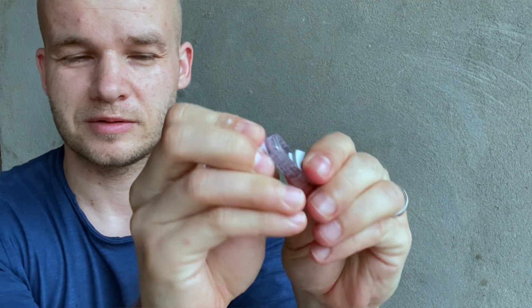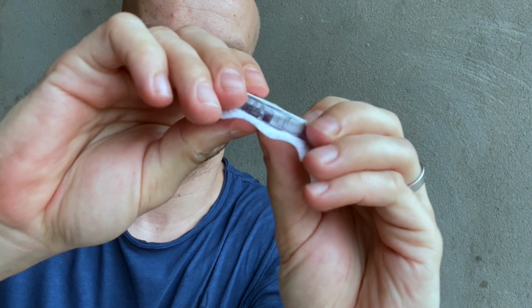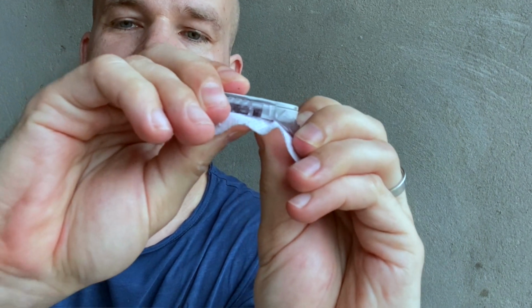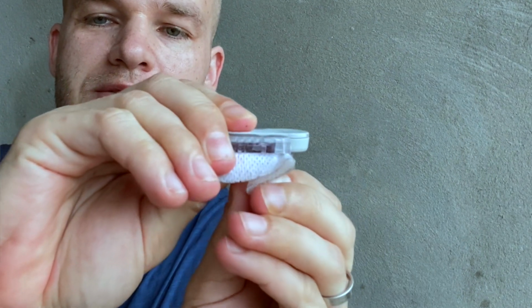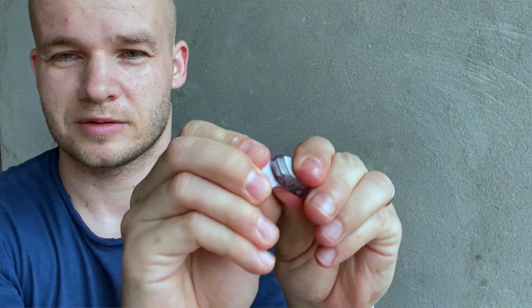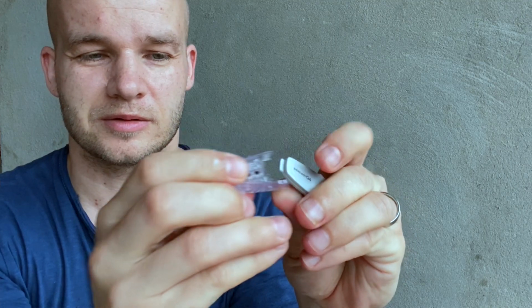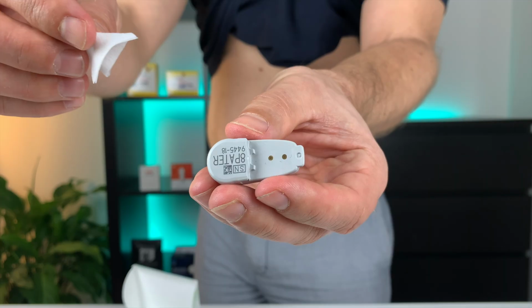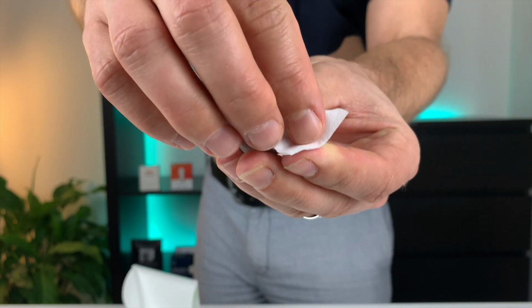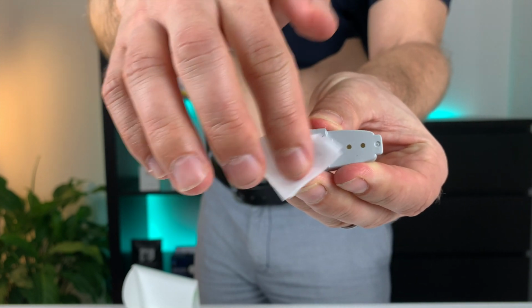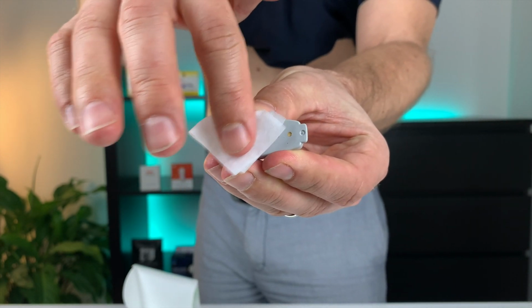You really want to do this because you can use the transmitter repeatedly with multiple sensors for up to 3 months, so you're going to need the transmitter for your next sensor. To separate the transmitter from the sensor, simply break off the oval part of the plastic holder in which the transmitter is sitting and pull out the transmitter. If there is any oily or sticky residue on the transmitter, wash it off with warm soapy water and clean it with an alcohol wipe so it's ready to use with your next sensor.